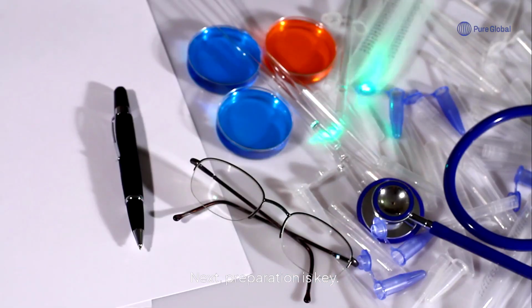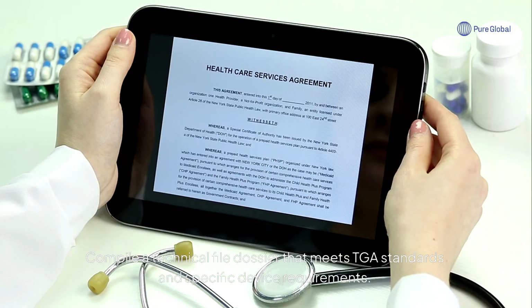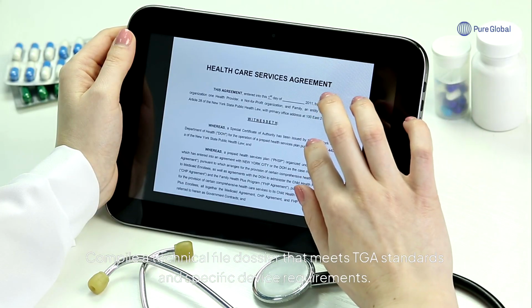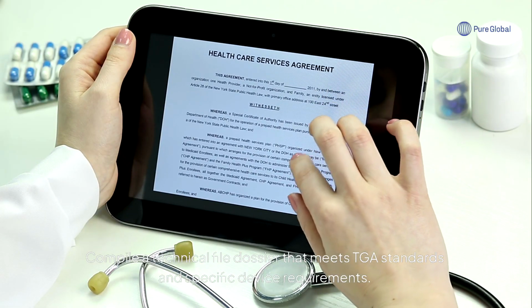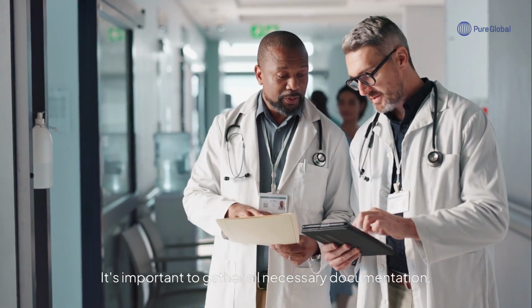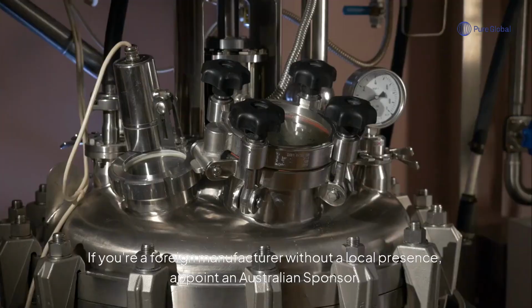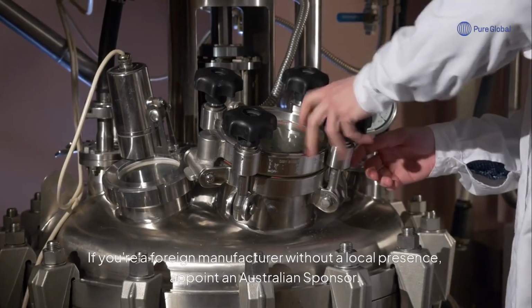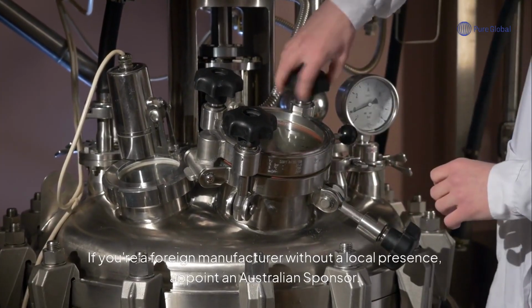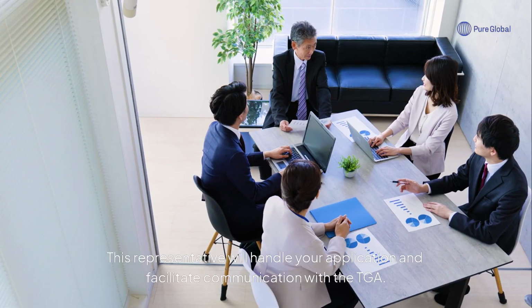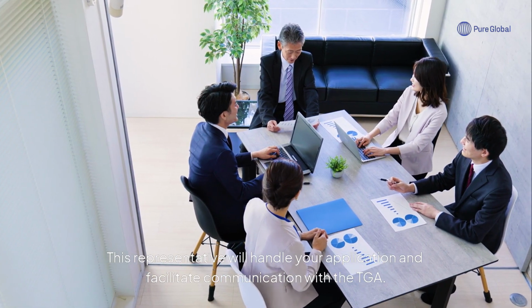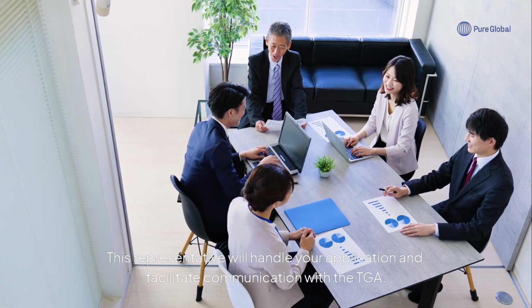Next, preparation is key. Compile a technical file dossier that meets TGA standards and specific device requirements. It's important to gather all necessary documentation. If you're a foreign manufacturer without a local presence, appoint an Australian sponsor. This representative will handle your application and facilitate communication with the TGA.